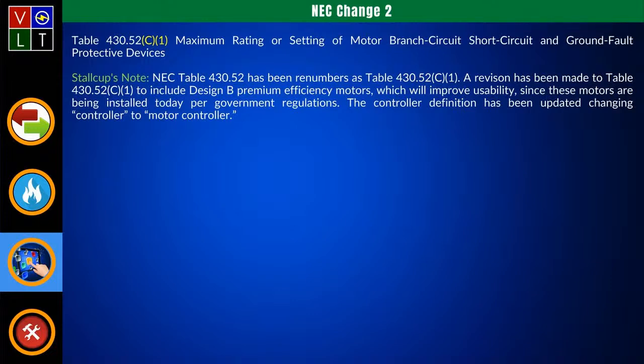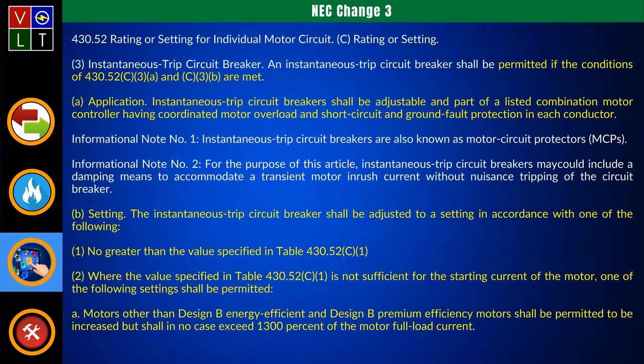Now the next one is 430.52C3, where we deal with an instantaneous trip circuit breaker. They're going to have a new part A for application, and part B for your settings. It's the same information, the only difference is these are no longer exceptions, they've been placed into full code text.